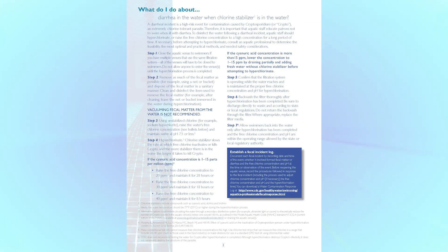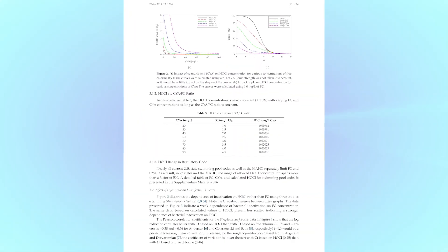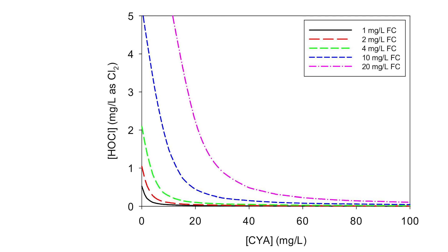CYA has a major impact on chlorine efficiency. Fortunately, even low levels of active chlorine can disinfect and prevent algae. If there is an accidental fecal release in a commercial or public pool, the CDC's recommendation is a maximum of 15 parts per million CYA. And as covered in course 3, achieving disinfection of diseases like cryptosporidium and giardia requires a certain amount of contact time with chlorine. With CYA over 15 parts per million, disinfection becomes impractical because the contact time goes way up.